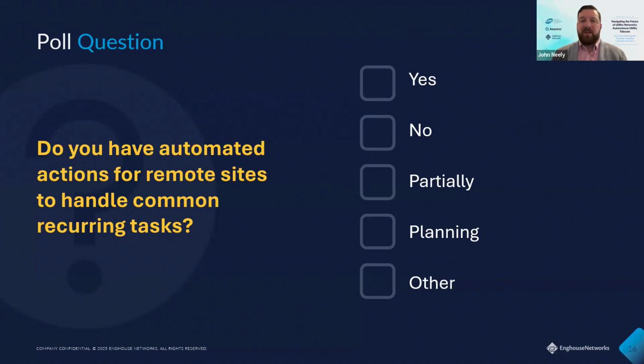A lot of times we'll have a fail-safe. Techs still have day-to-day control, but during an event, you can set a higher threshold for something, instead of just a high temp. Once you get to a very high temp, automation kicks in and does what it needs to do to cool down the site, as a fail-safe.